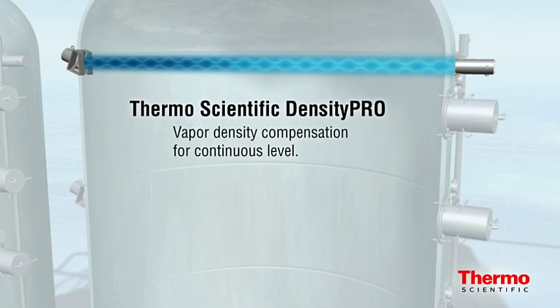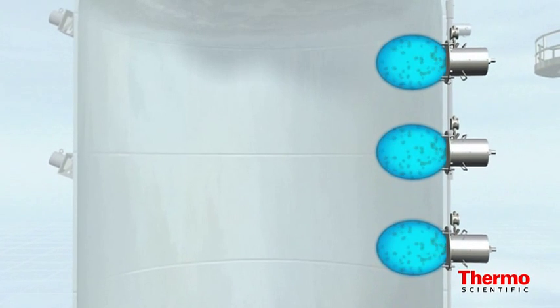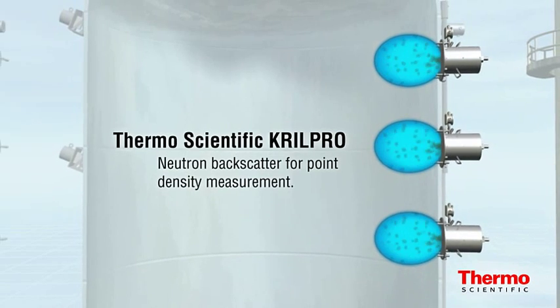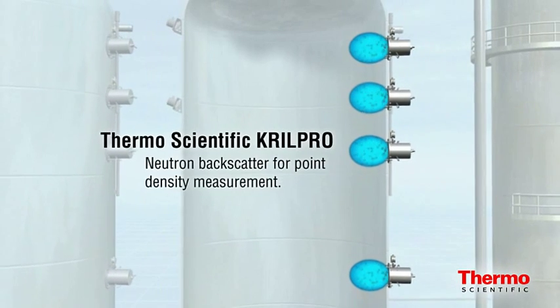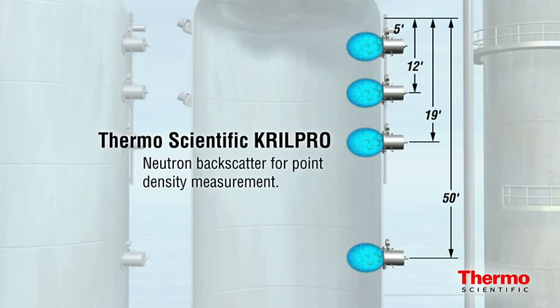Without vapor density compensation, refiners can inadvertently experience up to a ten percent level measurement error. At the heart of this coking control system is the Thermo Scientific KRILPRO. A 100-millicurie americium-beryllium source mounted inside the instrument directs high-energy fast neutrons through the vessel wall. The fast neutrons quickly transition to thermal neutrons, with some collected by the helium-3 detector. A picoamp current is then generated, which is amplified to produce an isolated 4-20 milliampere output signal proportional to the product's density.